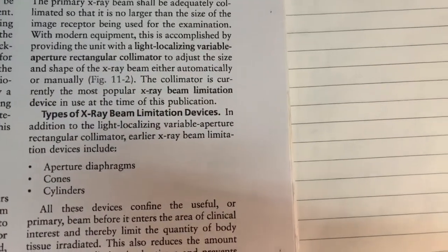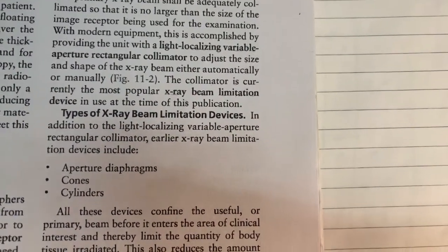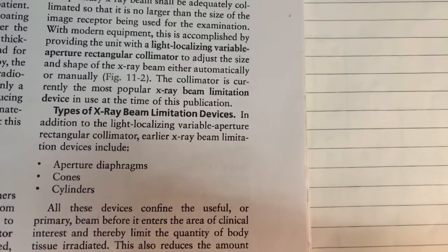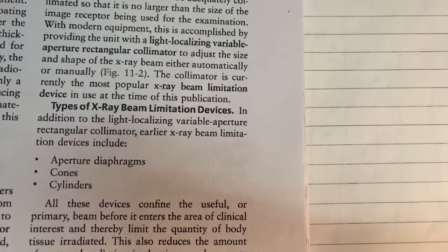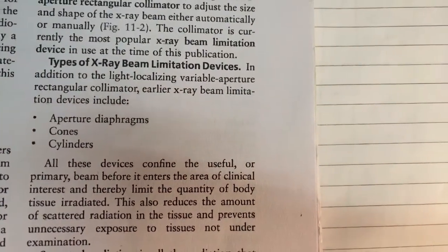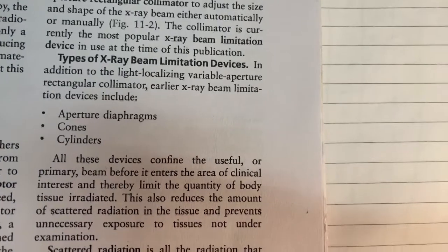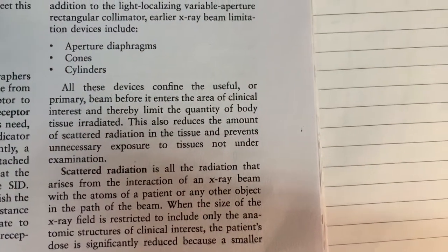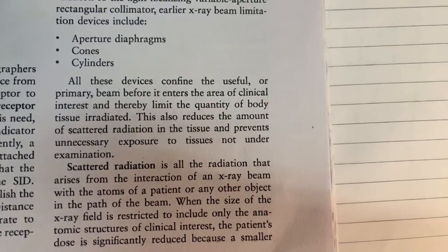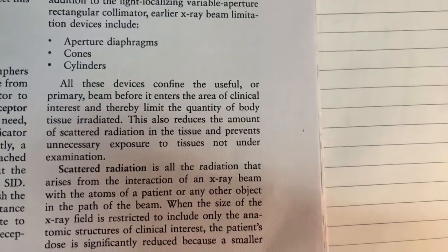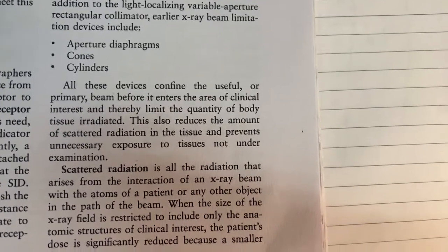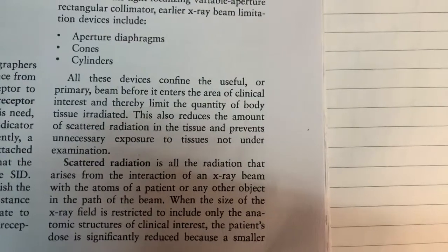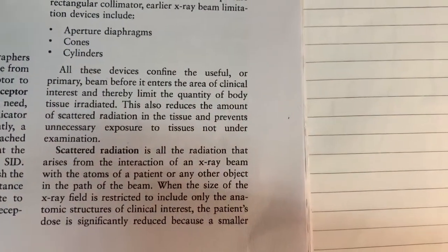In addition to the light localizing variable aperture rectangular collimator, earlier X-ray beam limitation devices include: aperture diaphragms, cones, and cylinders. All these devices confine the useful or primary beam before it enters the area of clinical interest, thereby limiting the quantity of body tissue irradiated.